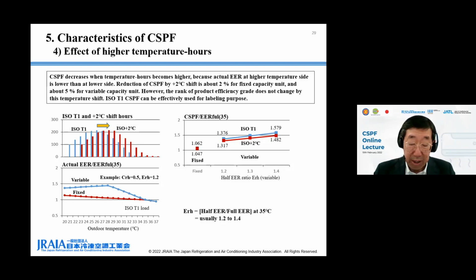CSPF decreases when temperature hours becomes higher because actual EER at higher temperature side is lower than at lower temperature side. The right figure shows CSPF divided by 35 degrees C full EER of ISO T1 and plus 2 degrees C shift hours for fixed capacity unit and variable capacity unit in usual range of half EER ratio from 1.2 to 1.4.